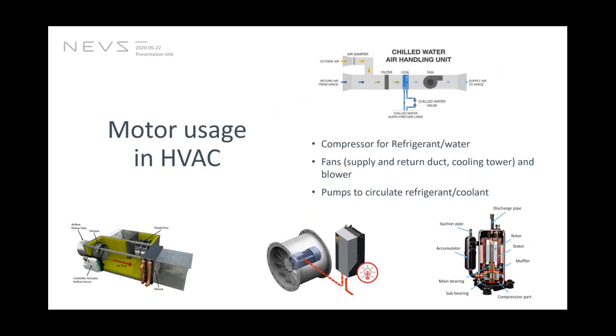So in the HVAC system, where are the motors being used? It is basically in the compressor, where you compress the refrigerant or any coolant. It might be water or some other coolant as well. Another application is for airflow control, basically in the fans and the blowers used in the air handling units. And the pumps which circulate the refrigerant and coolant. But in the further introduction, I haven't included the pumps in the refrigerant coolant loop because that's a different story compared to the HVAC application.